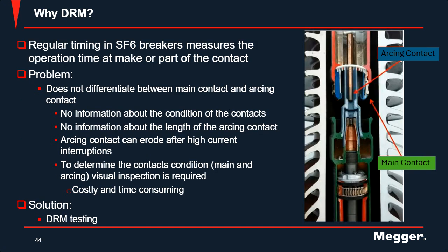So why do DRM? Well, I just talked about it. It's an easy test. You can use it with dual grounding. It is a separate accessory that you can use with your circuit breaker analyzer. It does have timing built in, so you can do a timing curve on it. However, it's going to be a resistive curve. It's not going to be as easy to follow as your conventional timing or the dynamic capacitance measurement would be. So if you do normal timing, like I said, you're not going to get any information about the condition of your contacts, the length of the arcing contact. The arcing contact can take a load of high current inputs. So in order to do that, you're going to have to do DRM testing.